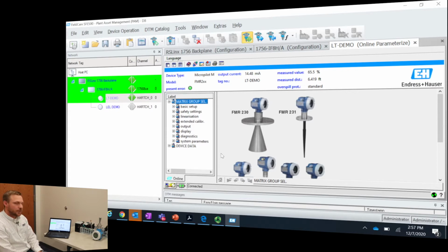We can see all sorts of information for this device, even more information than we could see with a HART communicator since we're using the software package. We can see the device type. This is an older type of radar, a Micropilot M. It's currently outputting 14.5 milliamps. That's 66% of its measured value of its scaling. We can see there's no present error on it. It's happy, it's green, there's no error conditions going on. We can see the tag number.